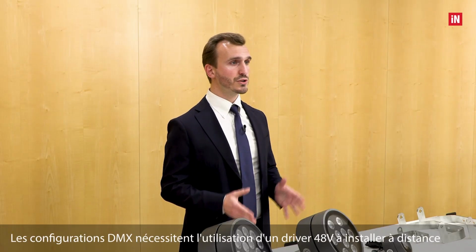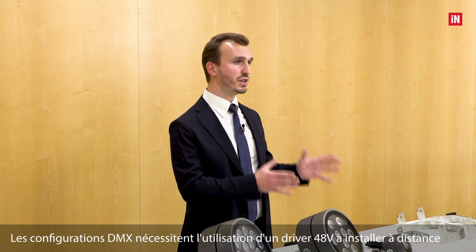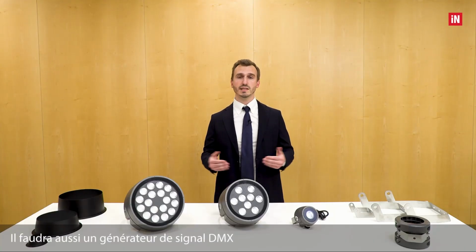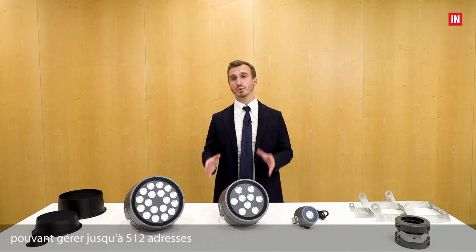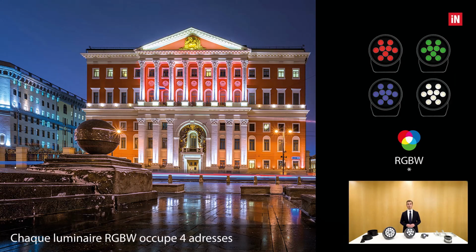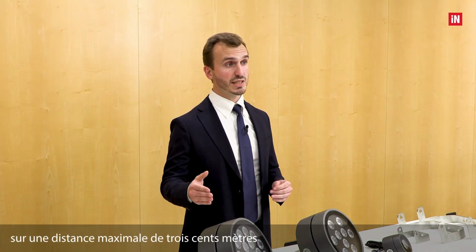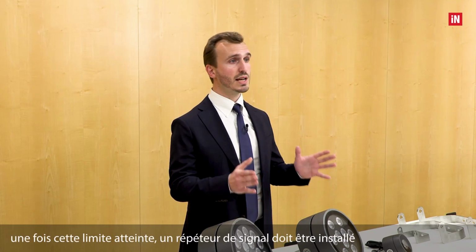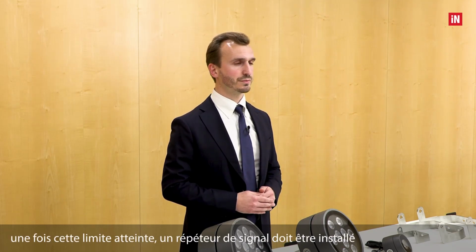The DMX configuration requires the use of a remote 48-volt low-voltage driver that will be installed externally to the luminaire. A DMX signal generator will also be needed, which can manage up to 512 addresses. Each RGB white fixture occupies 4 different addresses, so on each generator line we can connect up to 32 fixtures, over a maximum distance of 300 meters. Once this distance has been reached, a signal repeater has to be installed.